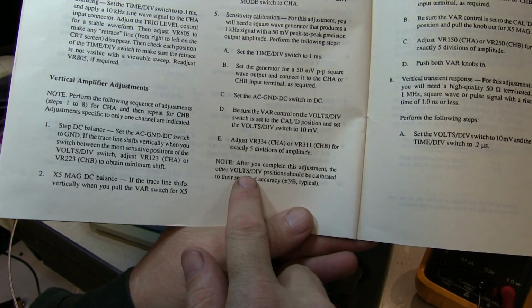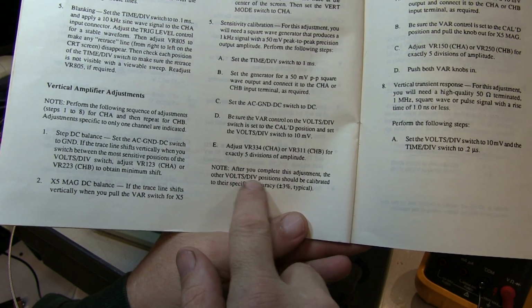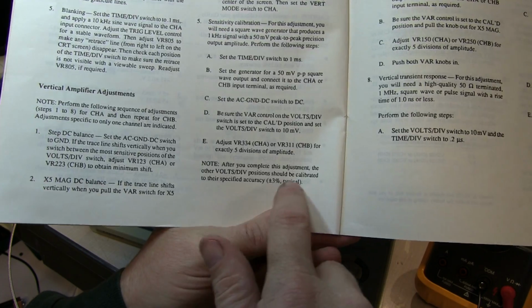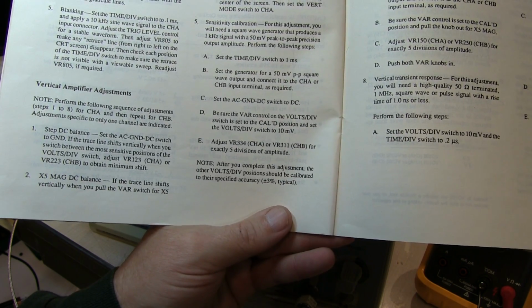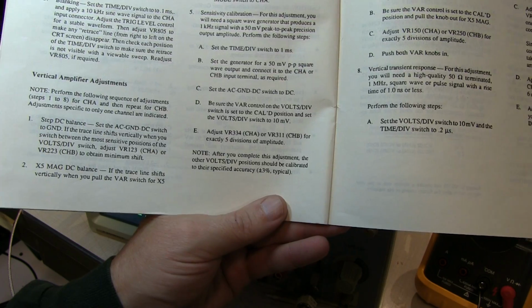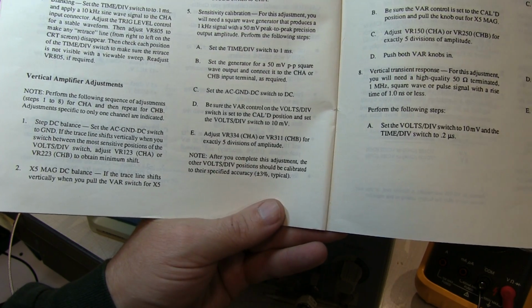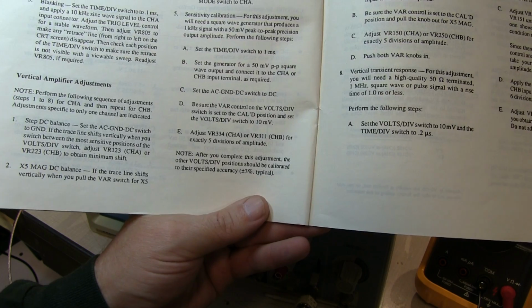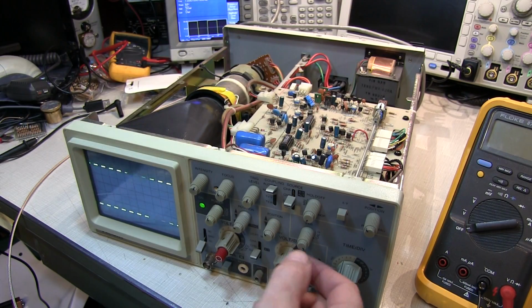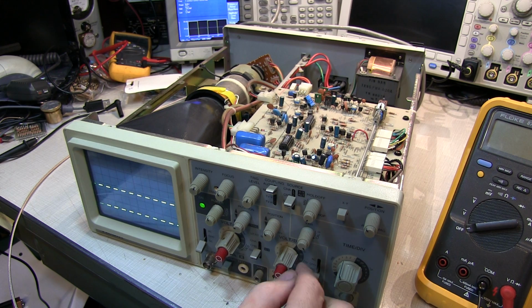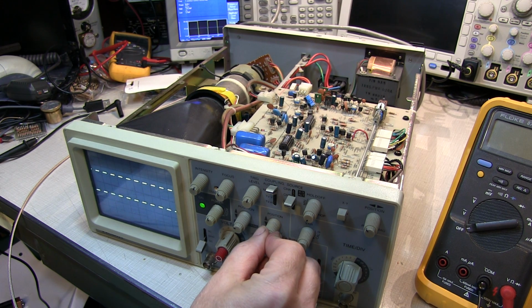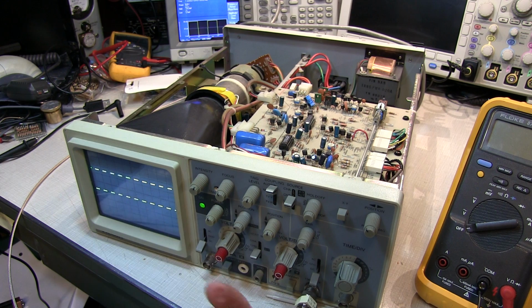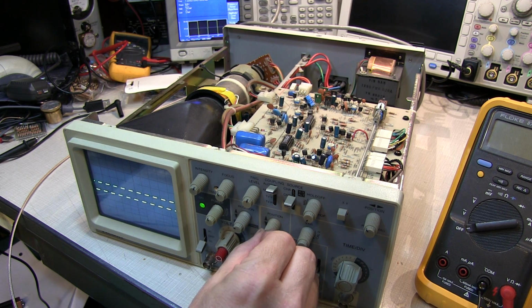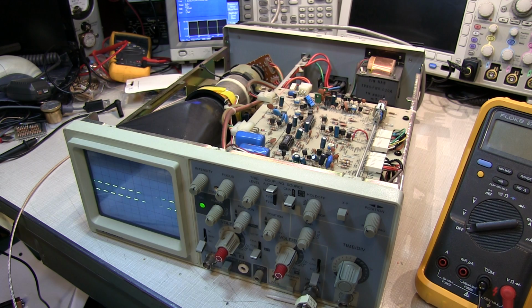Now, according to the instructions here, once we complete that adjustment, all of the other volts per division positions should be calibrated to within plus or minus 3%. They use precision resistors in the attenuators, so we're just making one gain adjustment to set everything right. So we should be good to go with that. Of course, we can validate this by going to a couple of different vertical positions. Say at 20 millivolts a division, I should have 2.5 divisions here, and we do. If I go to 50 millivolts a division, I should have exactly 1 division of deflection, and I do. Of course, we can change amplitudes and do that, but there's no need to do all that on camera.